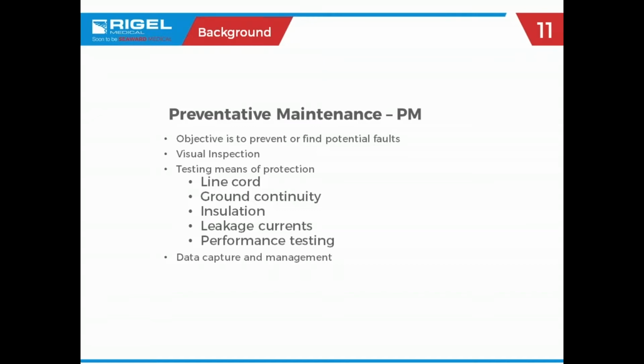And then you kind of go line cord, ground continuity, shake the line cord to be sure that there's not any loose connections in there. Insulation testing, if you're doing that, leakage currents, performance testing, data capture, and management.